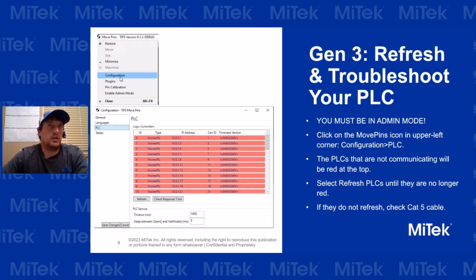Go on the back side of the box; we have a Cat5 cable coming in on each corner. Some of them will have 2 Cat5 cables, some of them will have 1. The ones that have 1 are just jumping to the box next to it, either to the left or to the right, depending on where your 24-port switch is at. If it's got 2, then you know that one is going back to the switch. If it's got 1, then that one just daisy chains to the next box. Check to see that it's plugged in, check to see if it's good. If you only have 2 PLCs down, then it's likely that the box before it is communicating, so the box next to it is the one that might not be communicating. So check your Cat5. That's kind of the main thing. Check Cat5 on the PLC.